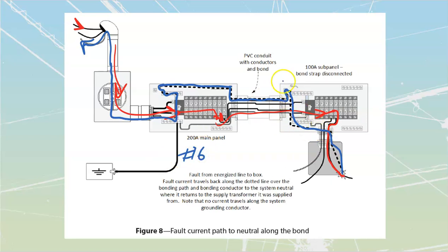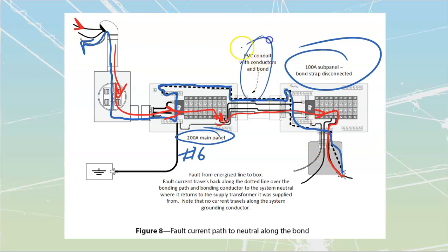But this one over here is going to be carrying a large amount of fault current, right? We've got 100 amps for this breaker over here. This one here is a 200 amp over there. This one's 100 amp, and so we've got a large amount of fault current that could travel through. So that bond is going to be sized large enough that it could deliver back all of the fault current for that 100 amp over there.